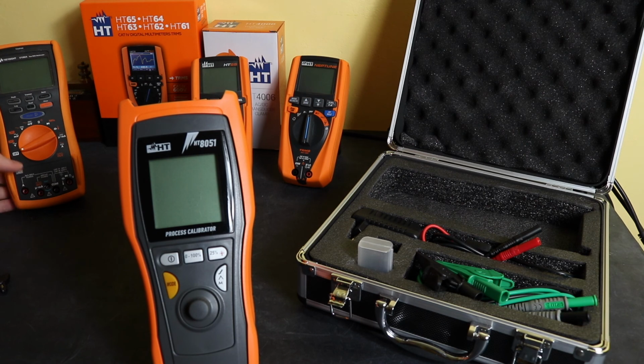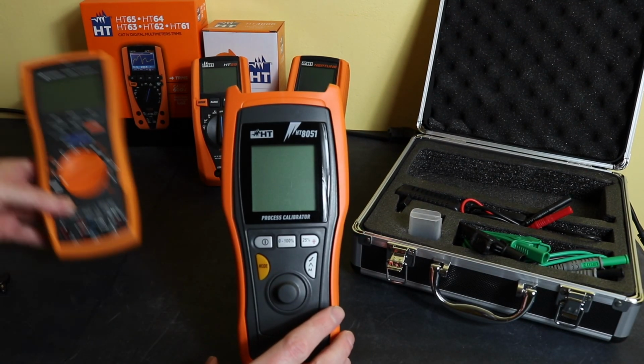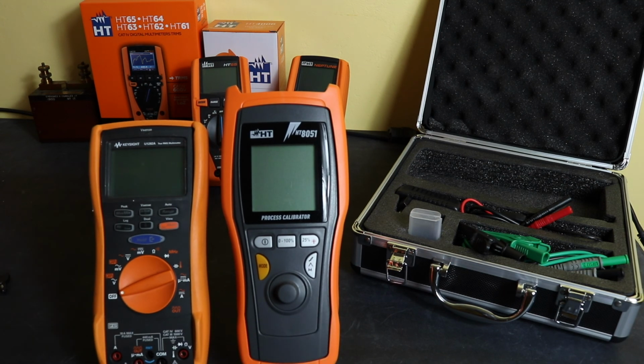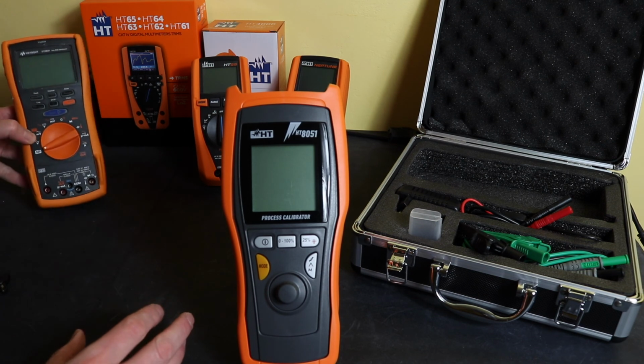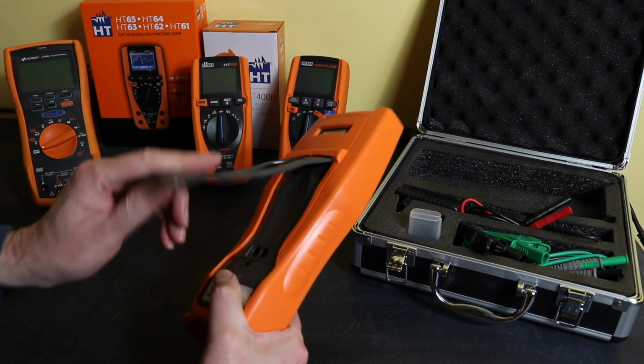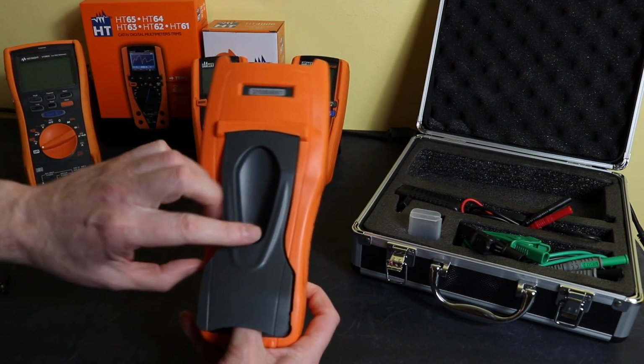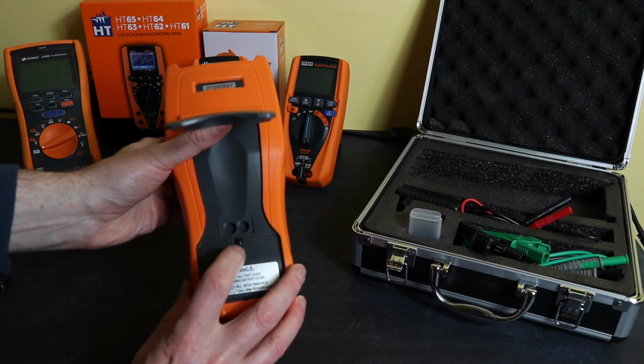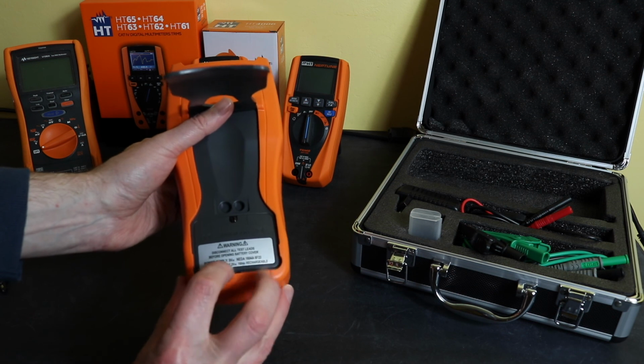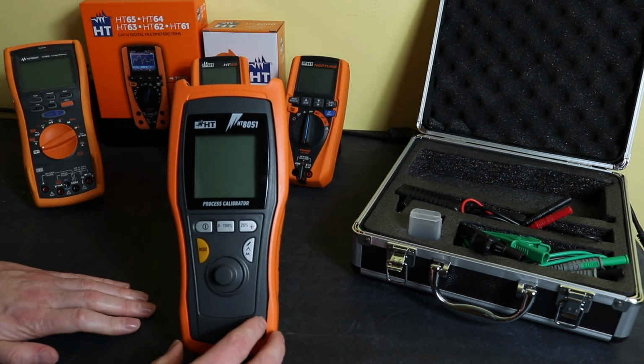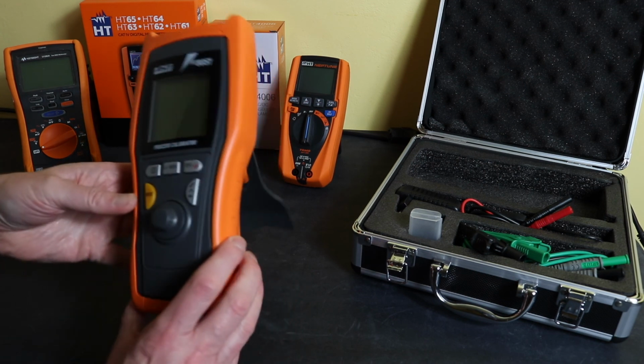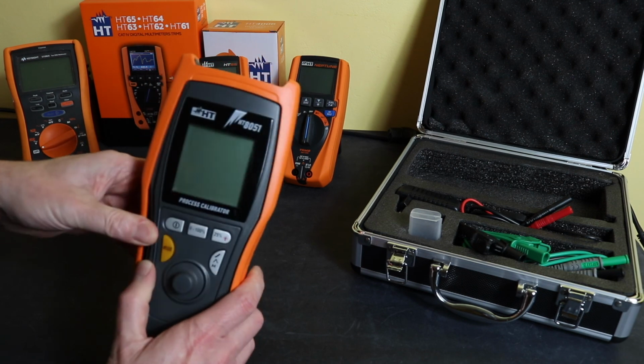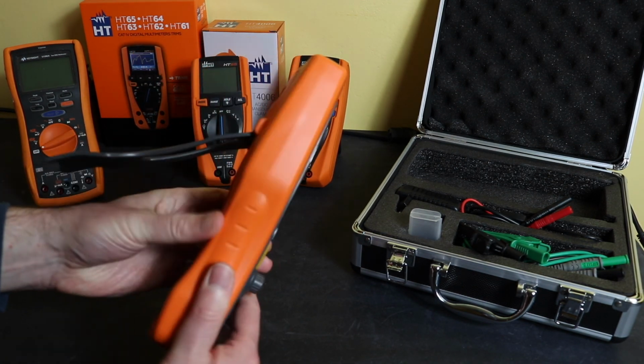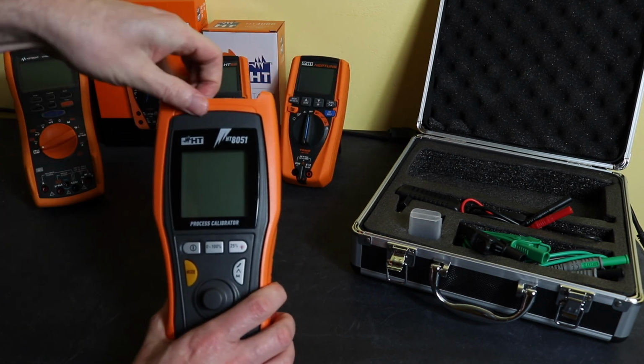The meter itself, it's a fairly sizable instrument. If I bring my U1282 in the picture as well, you can see it's about 3/4 of an inch taller than this instrument, similar sort of width and depth to the Keysight there, just that little bit taller. Tilt bail at the back, it is serialised here. Battery compartment is in there, so you can get into that and replace the battery either with a standard 9 volts or the 7.2 volt rechargeable battery. And at the front here, the instrument itself is in this little boot. The boot doesn't seem to fit too well really. It seems to stretch quite easily and then not go back into position. But it provides it with a little bit of protection, I guess.